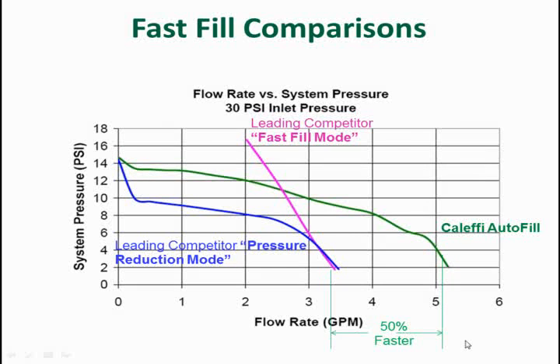So what that means is you don't have to build a bypass around this valve to get a fast fill that you're going to have to turn on and forget about, or risk popping your relief valve because you weren't paying attention to it. Just set this valve at the pressure you want. It's going to fast fill by itself. It's going to know when to shut off when it gets to the preset pressure. So it's a great little valve. If you haven't tried one, get out there and grab some of those and put them on your jobs.